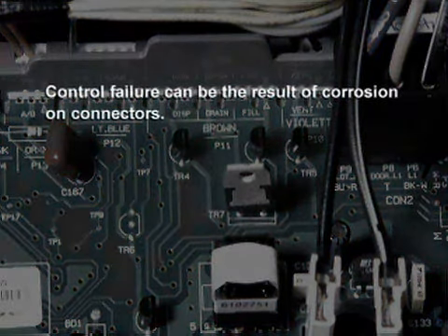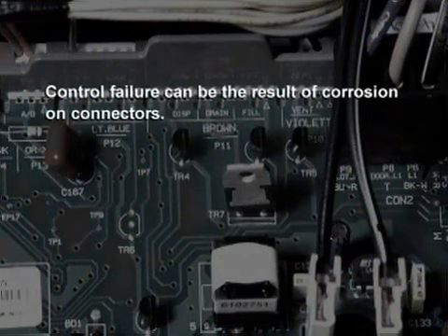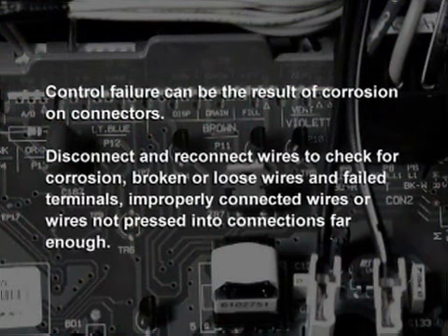Control failure can be the result of corrosion on connectors. Before testing any components, first disconnect and reconnect wires to check for corrosion, broken or loose wires or failed terminals, improperly connected wires, or wires not pressed into connections far enough.